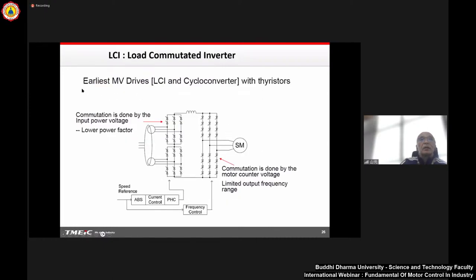This is an example of LCI, load commutated inverters, using thyristors for the inverter section and thyristors for the converter section. The current source drive controls the output voltage of the DC bus according to the synchronous motor speed. So as the synchronous motor speed is low, the DC bus voltage is also very low - proportional to synchronous motor speed.